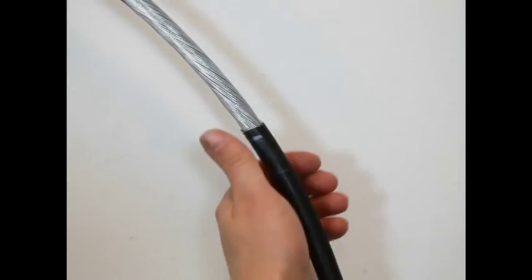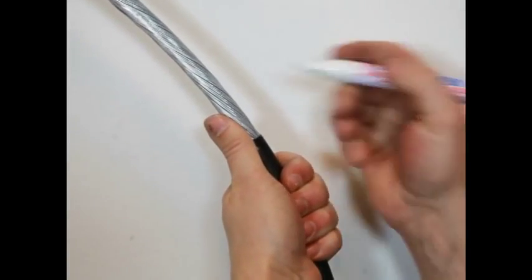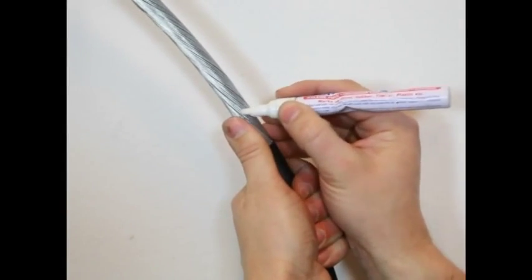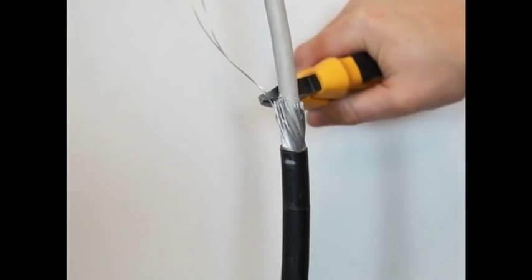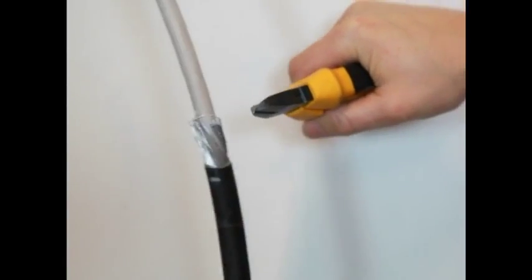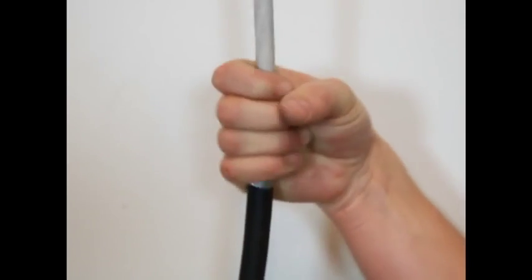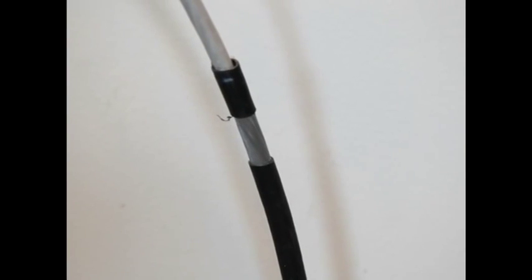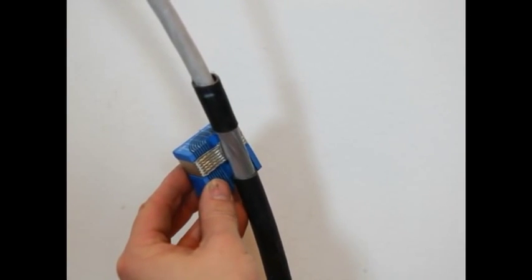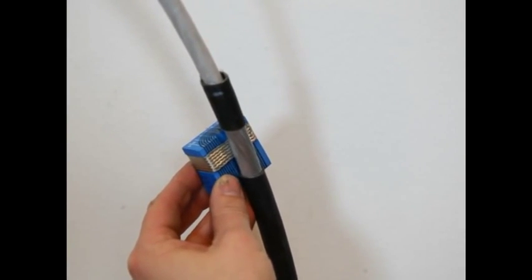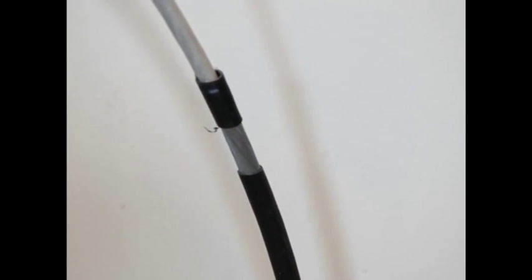Mark where to cut the armor and cut it. Slide the loose piece of cable sheath so that it covers the end of the armor. The exposed armor is to accommodate the whole braid section of the module. Make sure that the short piece of cable sheath is completely outside the module.